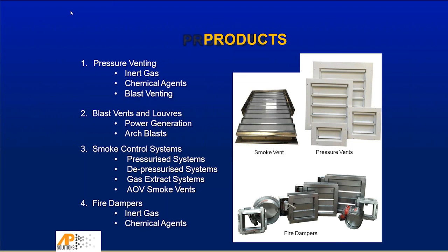We do a PV pressure vent and a PVD. The PV just means pressure vent. It's a one-way inert gas pressure vent. And the PVD is a pressure vent that's a dual flow. We've designed our latest version to give a free vent area of up to 90%. And I talk about this as a dynamic coefficient. The other way of looking at that is this resistance to opening pressure, where without a pressure vent, you might get a certain peak pressure within the room. You put a pressure vent in that hole, and you will get an increase in peak pressure within that room. The difference is the dynamic coefficient, which we use, and I haven't found any other company that has tested to find out what theirs is. We've tested some other products to see what they are, so we do have a good understanding of that.